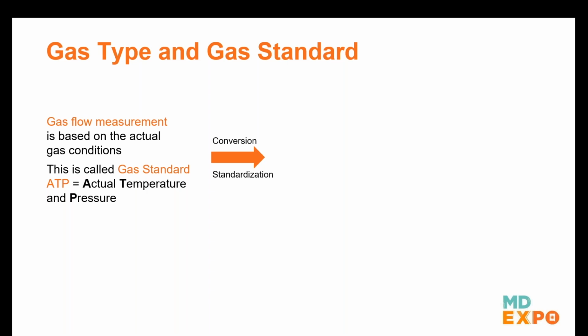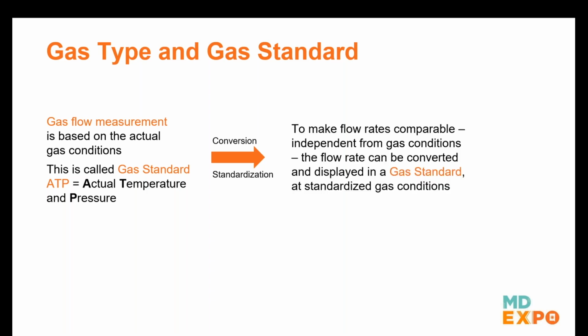Has anybody else heard of other gas standards besides ATP? Anybody heard things like ATPS, BTPS, STP? There's about 17 or so recognized gas standards out there. So you might have to do a conversion, or your analyzer might have to do a conversion, so that you can compare apples to apples, right? Let's talk a little bit more about that. But be aware that we may measure the gas very accurately at ATP and display it as another gas standard. That's the biggest takeaway from this one, okay?